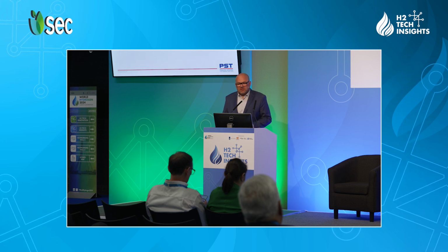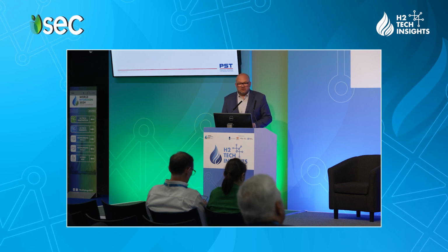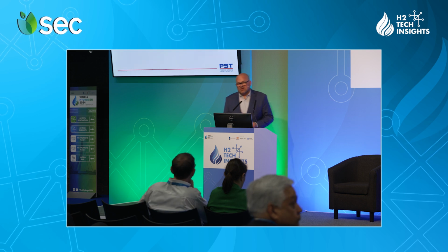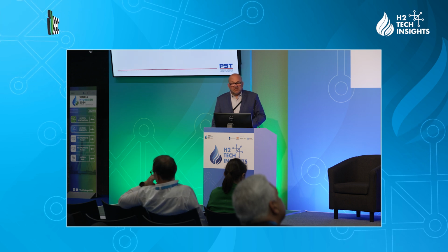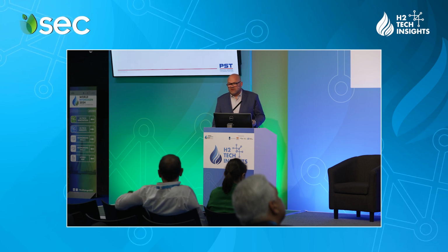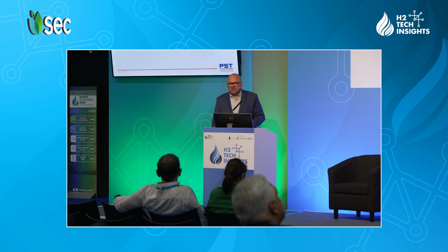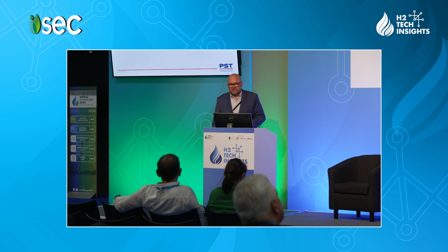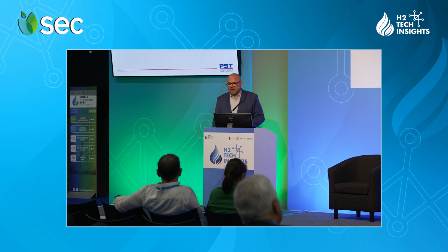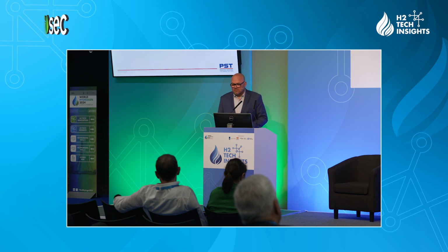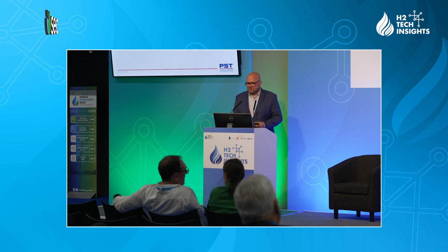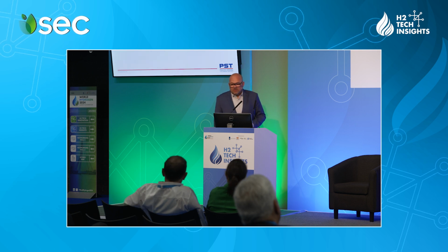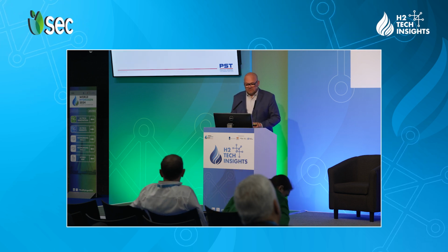So you need a sample system to condition the sampled gas. You need to do pressure reduction, usually cooling or heating even, filtration. You need functionality interlocks like liquid detection, so that you do not flood equipment. You don't want to be flooded with water. So this is just an example of a high-end system supplied to a customer, where you see both measurements on one panel.